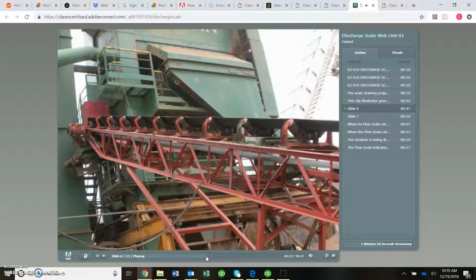Notice the belt scale in the middle of the conveyor. This was an attempt to weigh the material into the mixer. This did not work well since the weight was being totaled in the middle of the conveyor, and the batch control would shut down the conveyor feed with half the conveyor full of weighed product. If the feeder feeding this conveyor fed it evenly, this may not be too big of a problem.